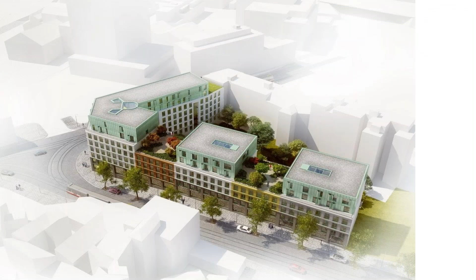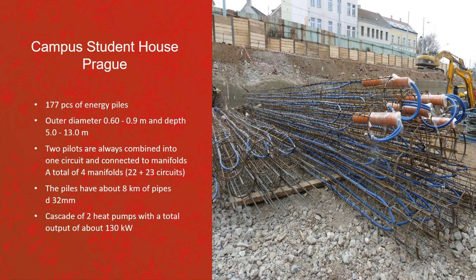Heat and cool are used from 177 energy piles. The outer diameter for the piles is 60 to 90 centimeters, and the depth is 5 to 13 meters. 2 piles are always connected to one circuit and connected to manifolds. A total of 4 manifolds are installed. The piles have about 8 kilometers of pipes with a diameter of 32 millimeters. And the production of heat and cold is provided by a cascade of 2 heat pumps with a total output of about 130 kilowatt. That's all for this project.